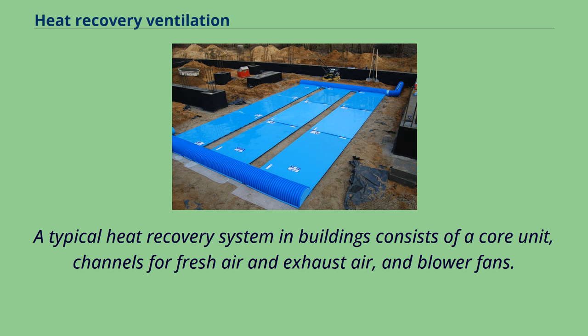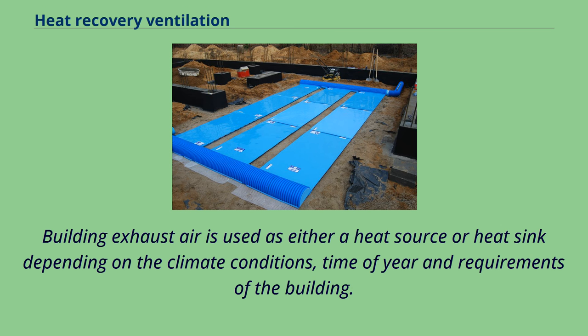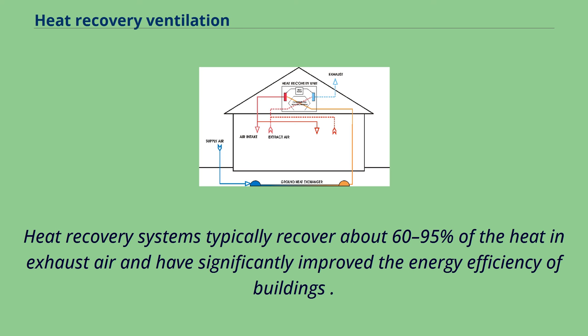A typical heat recovery system in buildings consists of a core unit, channels for fresh air and exhaust air, and blower fans. Building exhaust air is used as either a heat source or heat sink depending on the climate conditions, time of year, and requirements of the building. Heat recovery systems typically recover about 60–95% of the heat in exhaust air and have significantly improved the energy efficiency of buildings.